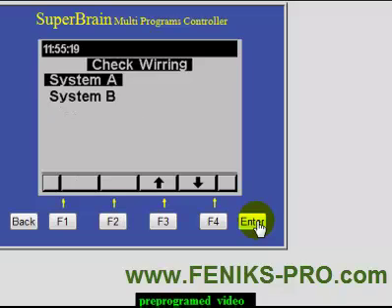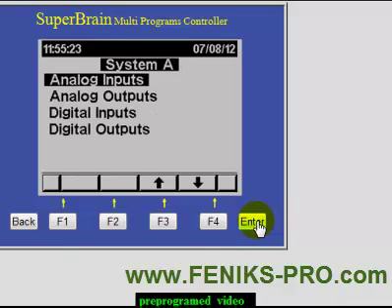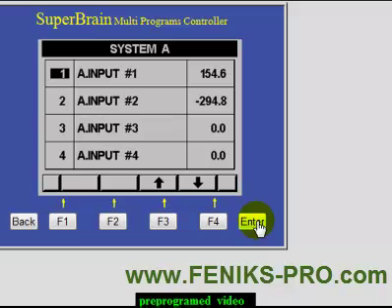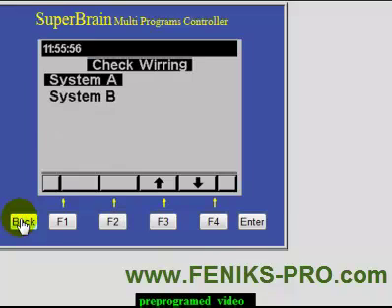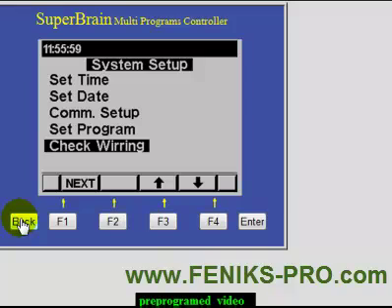You can check wiring to verify everything in the installation is alright. Let's select System A — we have analog inputs. Here you can see that inputs one and two are installed and working correctly, but the number is very high because I don't have any sensor installed on my SuperBrain. That's how you check your wiring. If you have four sensors, there should be four sensor values displayed in check wiring for analog inputs.